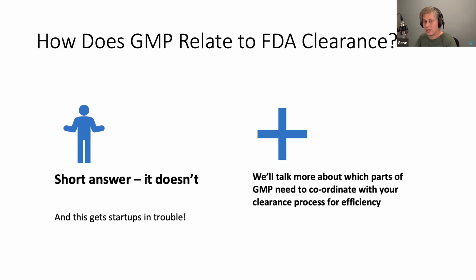So this gets a lot of companies into trouble because they can find themselves in a situation where they've gotten 510K clearance, but they haven't actually done the things that they're going to need to do before they put the device on the market. That's why we call a 510K a pre-market notification. It's just a notification and an agreement with FDA before you go to the market. It doesn't mean that all of the things that have to be done for that device to go on the market have necessarily been done. It's a major hiccup. We'll talk in a minute about which parts of GMP are needed to coordinate with your clearance process for efficiency. But this is an important point. If you're bringing a device to market, you've got to worry about clearance and you've got to worry about quality system requirements. They're not perfectly blended together. So keep that in mind.